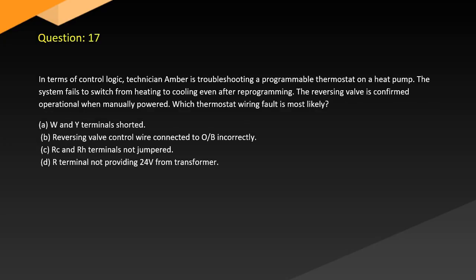Question 17. In terms of control logic, technician Amber is troubleshooting a programmable thermostat on a heat pump. The system fails to switch from heating to cooling even after reprogramming. The reversing valve is confirmed operational when manually powered. Which thermostat wiring fault is most likely?